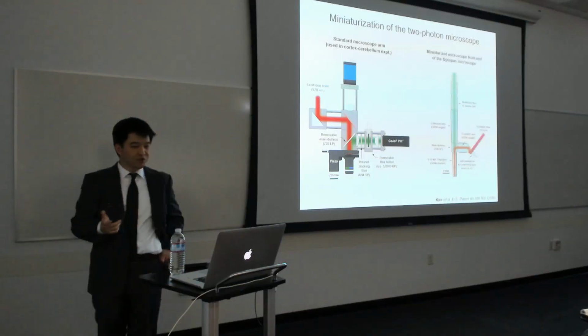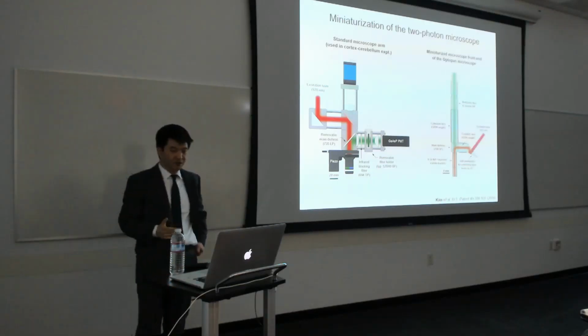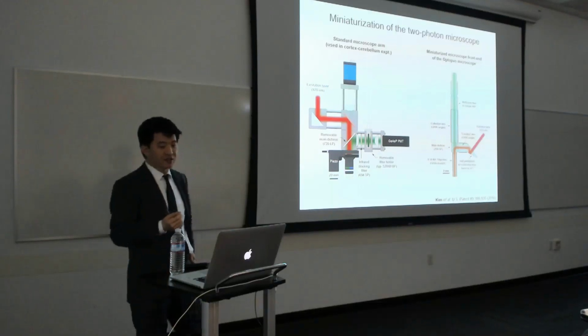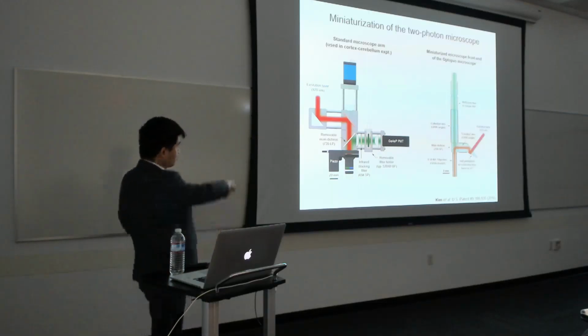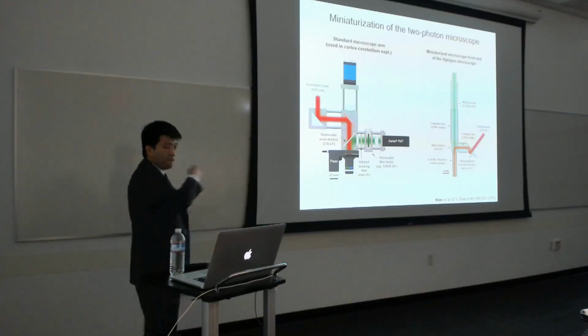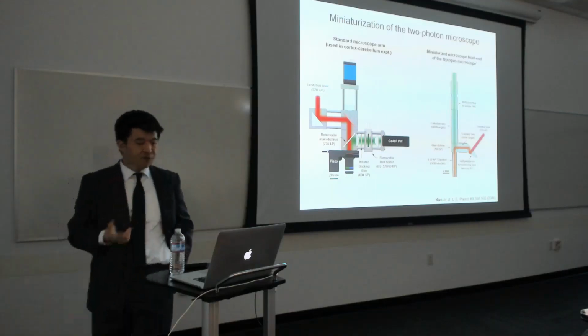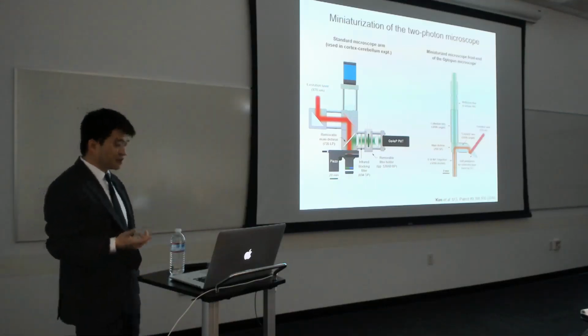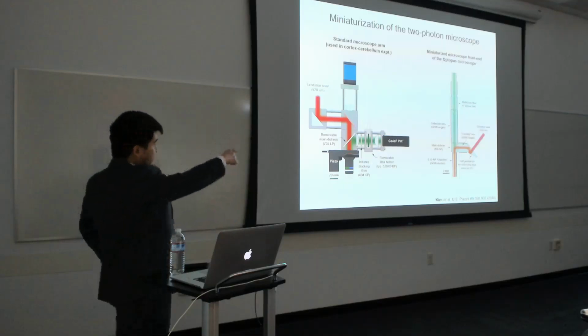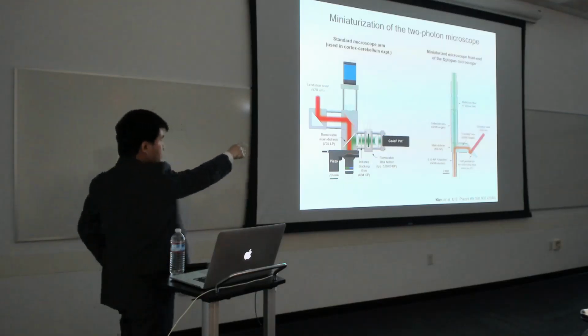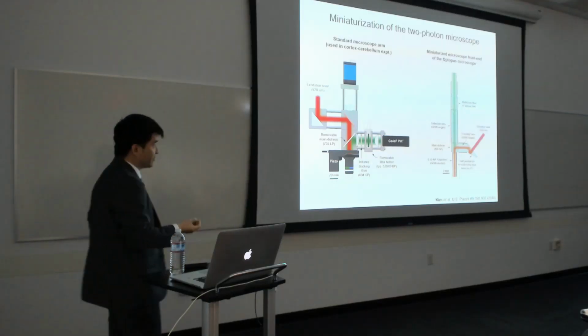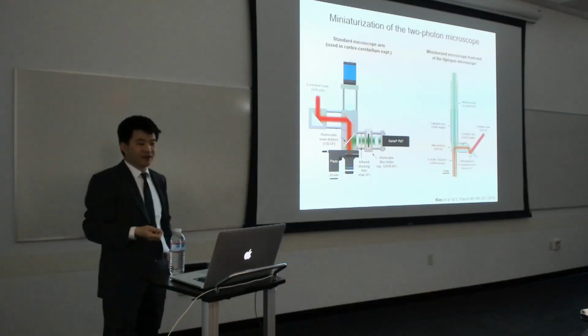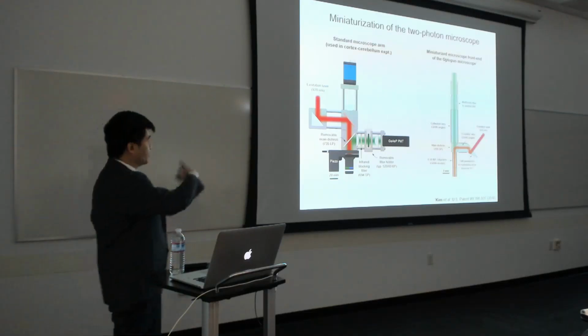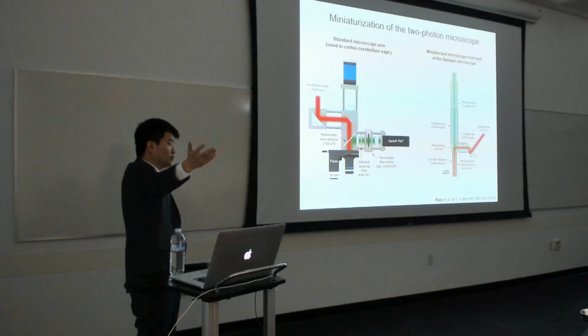So using micro-optic construction, namely GRIN lenses and microprisms and so forth, we reduce the physical size of a 2-photon microscope front end from 20 millimeters down to 2. The miniaturized front end also implements the standard 2-photon microscope architecture, again, where the excitation laser is brought in now from the side and couples into the micro-optic objective. And we also have a collection path for sensing emitted photons from the sample and to distribute it to a remotely located photomultiplier tube.